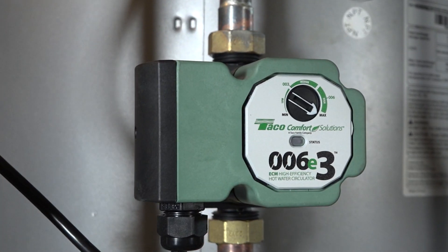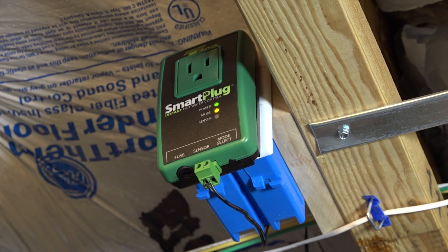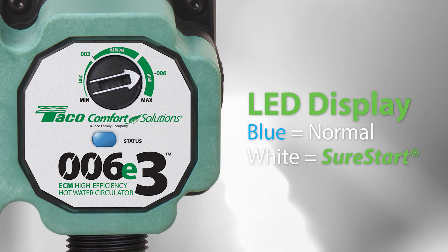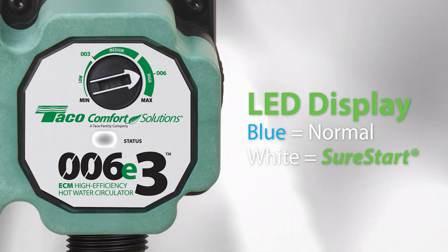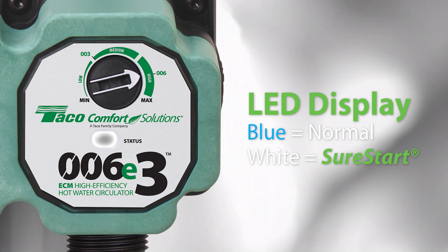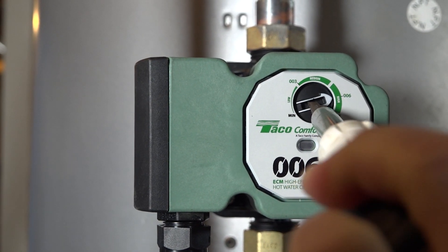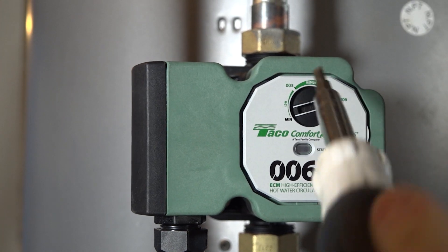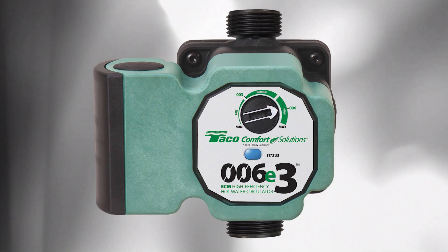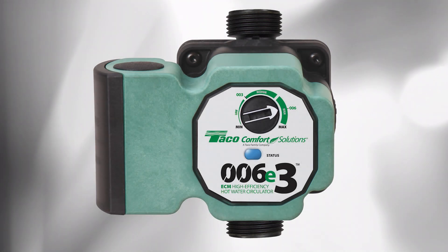Now that you've finished installing the Smart Plus E system, let's make sure that it's all lit up and working correctly. For the 006E3, the blue LED will illuminate if the system is functioning normally. If the LED flashes white, the pump has detected air in the system and will automatically purge it using its Sure Start feature. The 006E3 has a dial to adjust the pump's speed so that it corresponds with the requirements of your system. If you're replacing a Taco 003 or 006, the 006E3 has performance points on the device so that replacement is even easier.